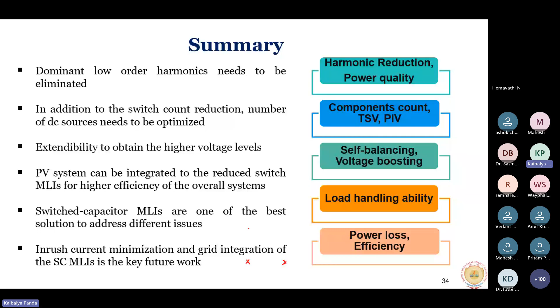The major issue is that let us say you have a PV panel and this inverter structure, whether it is a multi-level inverter or any single stage inverter. If you try to avoid the transformer also, between this PV and the grid side neutral, there exists a parasitic capacitance. So what will happen is, through this grid negative, grid neutral to the PV side negative part, there will be a flow of leakage current. This is called leakage current, and it flows because of the common mode voltage issue that arises.